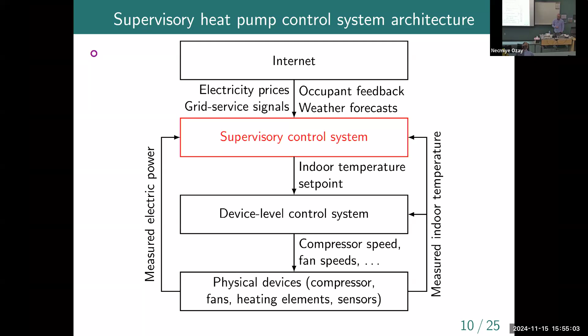The heat pump is a variable speed machine, so the device level manufacturer controls typically use PID with some saturation nonlinearities, rate limits, and things like that. It imperfectly tracks the indoor temperature set point, but if we don't make huge step adjustments, the tracking is usually pretty good. Because we're working at about 15 minute timescales, the faster transients from the device level control system tend to wash out. But we can model those, and in the second problem I'll show, where we were working at faster timescales, we actually did model those low-level dynamics. This control system tunes compressor speeds, fan speeds, looking at RPMs of different motors and things like that.